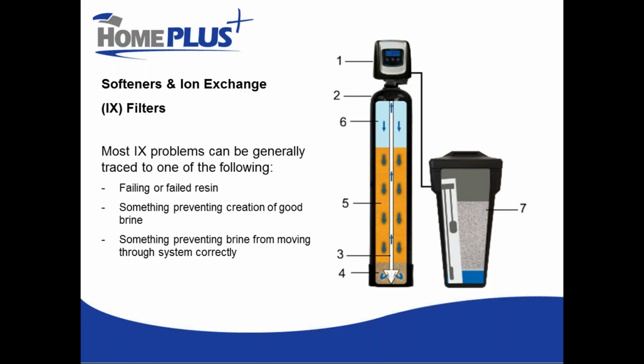So most of the problems in ion exchange can be traced to a loss of capacity in the resin. It's simply failing and it no longer has the capacity that it used to have originally. And at some point that capacity will get to the stage at which it's no longer cost effective or productive to continue to run it, and it simply needs to be replaced. Other times, there's something in the process that's preventing the creation of a brine solution. I'll explain what that is in a minute. That is effectively strong enough to do its job. And the last problem is something is preventing that brine from moving correctly through the system.